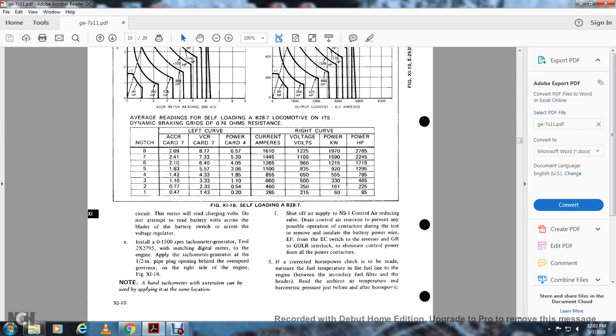If a corrected horsepower check is made, measure the fuel temperature in the fuel line between the secondary fuel filter and header. Read the ambient temperature and barometric pressure just before and after the horsepower check.